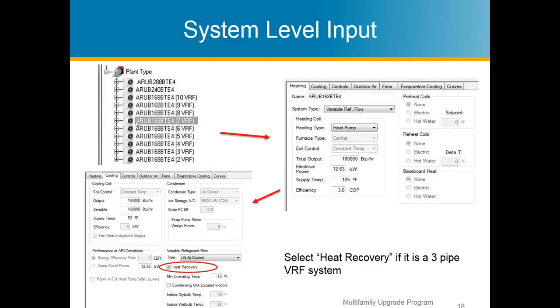So here's an example. You have your system tree, about the building tree, the system level, and you're putting in your heating, and you're putting in your cooling, and you're calling it a heat recovery system. So this is the total heating and cooling capacity of that big outdoor, or the larger outdoor unit. In the example I showed you is a 168 MBH outdoor unit. There's 4 of them. So this is that one system that's serving multiple indoor units. Heat recovery, you want to make sure you're selecting that if that's your 3-pipe system. If it's a 2-pipe system, it's not going to be a heat recovery system, and the modeling inputs are going to be similar to what you have for your conventional. However, you're still going to have that indoor unit you need to put in.